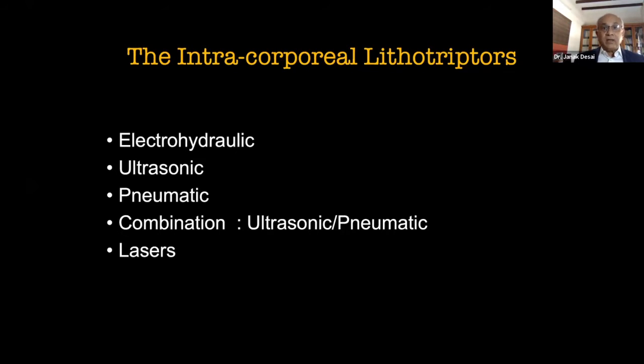Anyway, and finally, the combination came up. We realized the value of ultrasound with pneumatic. And once again, EMS came up with a combination that lets you use ultrasound if you like, use pneumatic if you like, because ultrasound had an inherent advantage of adding suction to it. You break, and at the same time, you pull out the fragments, which pneumatic could not. But pneumatic was a stronger energy. It could break very hard stones and faster. So you could take advantage of either one in the form of a lithoclast master.